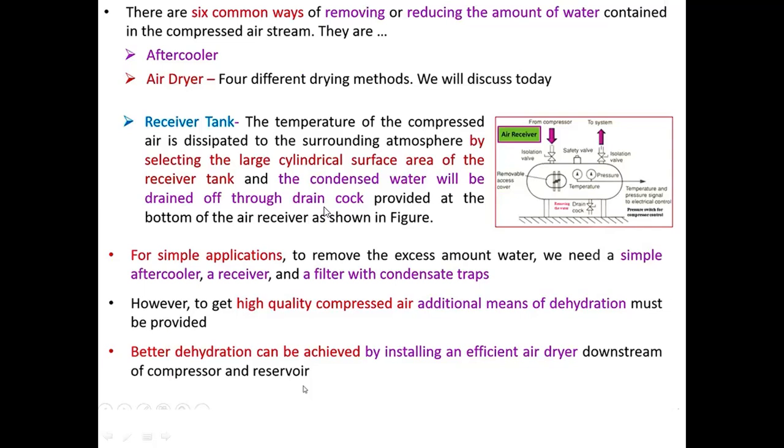For simple applications, to remove the excess water, we need a simple after cooler or reservoir and filter with condensate trap. However, to get high quality compressed air, additional dehydration must be provided. Better dehydration can be achieved by installing an efficient air dryer downstream of the compressor and reservoir.